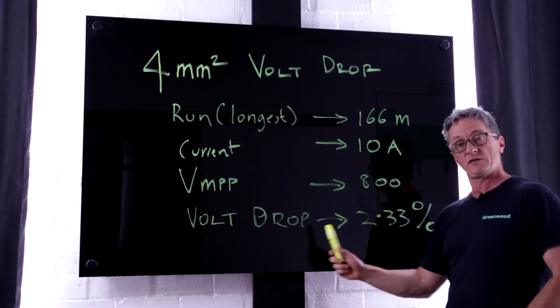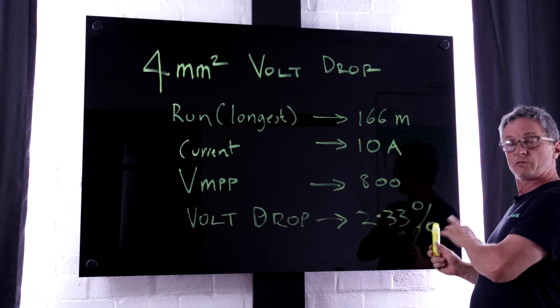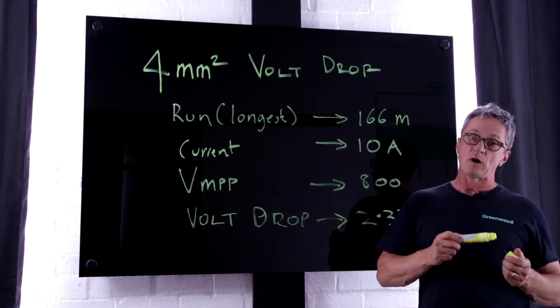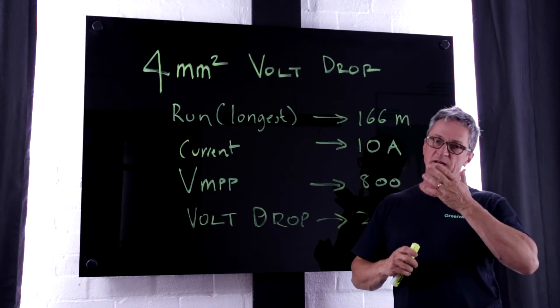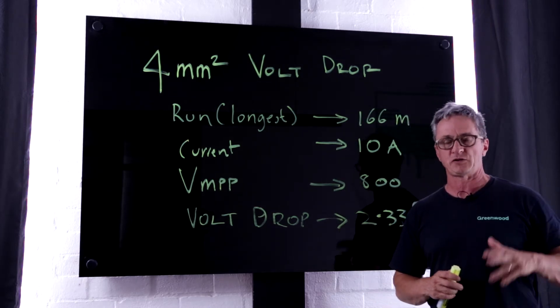The volt drop percentage in this case is 2.33%. Now it probably will be higher because we haven't taken into consideration some bends dropping down into the trench and a few other things.